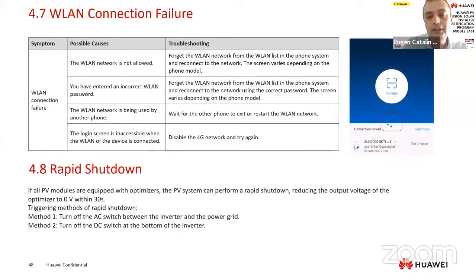We have a rapid shutdown function using the optimizer. We have 2 methods to activate this rapid shutdown. One is to turn off the AC. The second one is to turn off the DC switch of the inverter, and the voltage from the DC will go to 0 within 30 seconds.